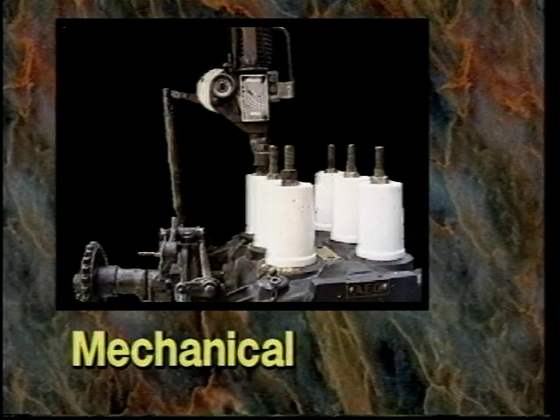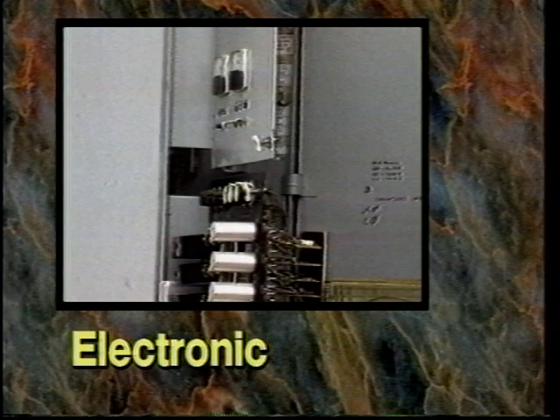Mechanical type is a mechanically operated trip piston which lifts a rod one notch at a time to accomplish sequencing. Electronic types of control utilize solid-state circuitry to provide the intelligence for performing all of the command functions for automatic operation.